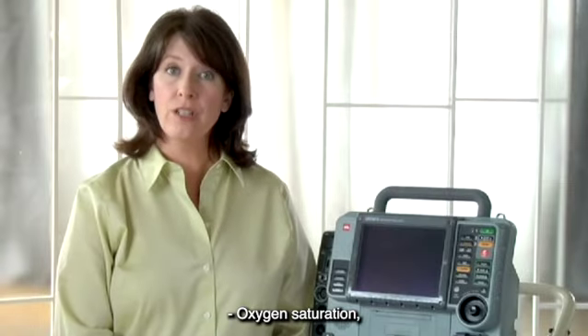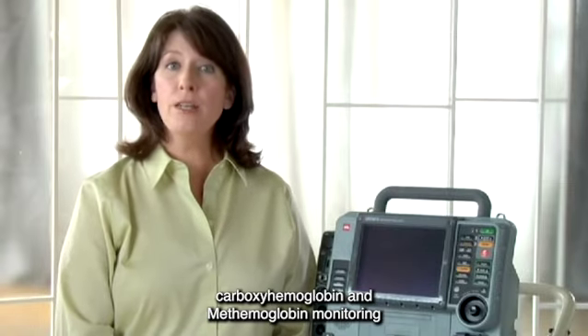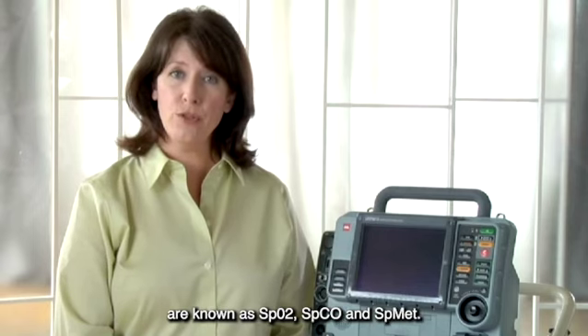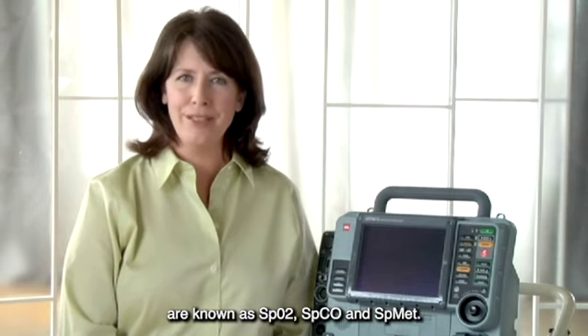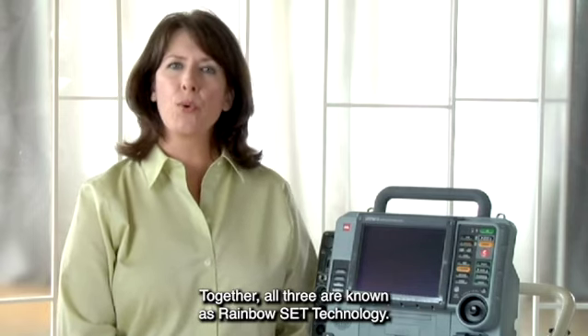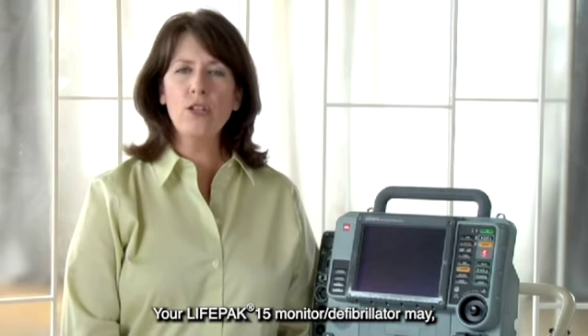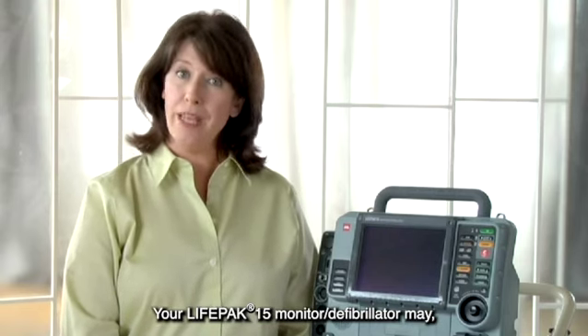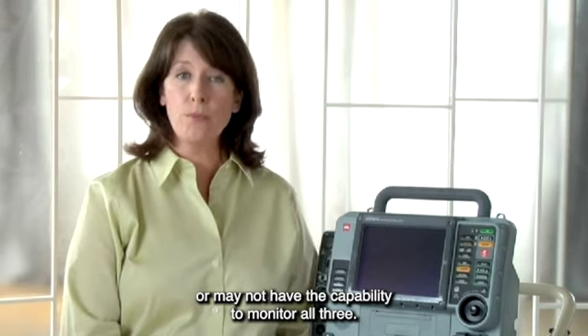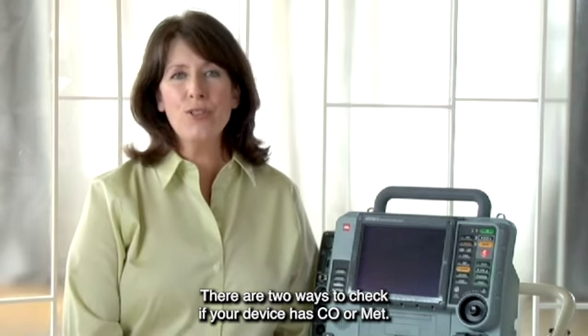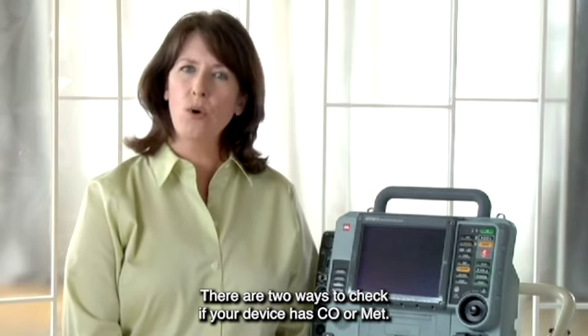Oxygen saturation, carboxyhemoglobin, and MET hemoglobin monitoring are known as SpO2, SpCO, and SpMET. Together, all three are known as Rainbow SET technology. Your LIFEPAK 15 monitor defibrillator may or may not have the capability to monitor all three. There are two ways to check if your device has CO or MET.